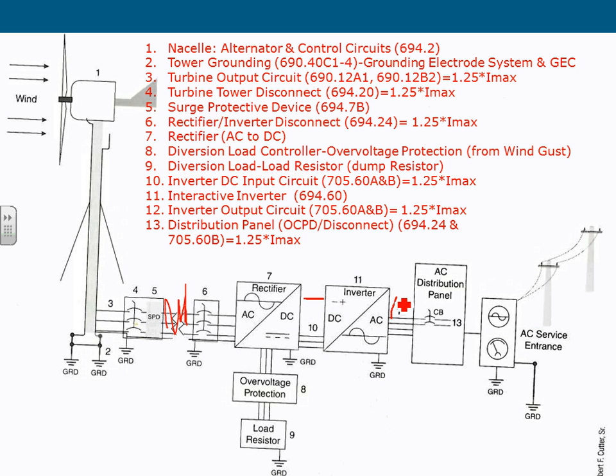And then here is where you get your so-called sinusoidal wave. First you take whatever voltage and frequency you get out of this unit and bring it to the rectifier. The reason is that you get to control the frequency by converting into DC. These are bridges, typical of what you have in my laptop right now. We're taking AC, converting it to DC. At this point, you bring it back from rectification and invert it back to AC, because most of the loads that we use are AC. You dump it into the grid.